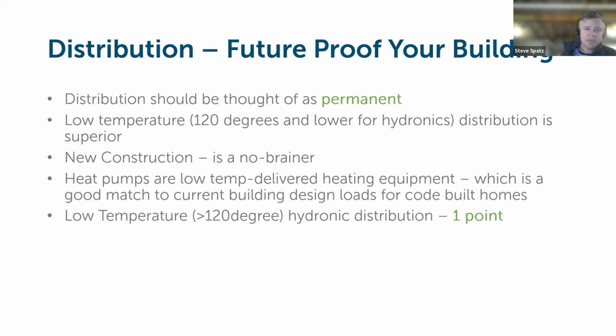And no matter what type of equipment is being used in the house, from a heating standpoint, we should really be thinking about the distribution system that's attached to that equipment as a permanent asset to the building, and it should be designed to be resilient for what's currently available for equipment and/or anything that may come down the line. Heat pumps are low ambient temperature delivery equipment. They deliver heat efficiently, but they don't deliver high temperature heat, which is what we've become accustomed to with fossil fuel equipment. So as long as you're designing a distribution system that's based around low temperature delivery, whether it's water or air, you're going to have the most flexibility for using heat pump equipment, and you're also going to get the highest efficiency possible out of any fossil fuel equipment as well.